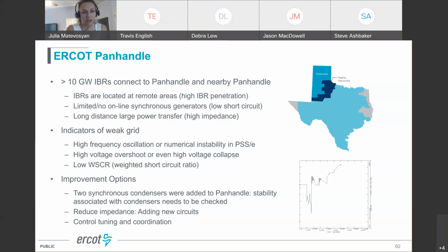What we've seen as indicators of weak grid is high frequency oscillation or numerical instability when we try to do dynamic simulations in PSSE. We can see high voltage overshoot or even high voltage collapse during fault simulations right after the fault is cleared. And if we do a screening type of calculation and calculate the short circuit ratio, and here you can see the weighted short circuit ratio, I'll talk about this term a bit more on the next slides. But basically, if we estimate short circuit ratio for this area, then we see that this area has low short circuit ratio, and that's a sign of weak grid.